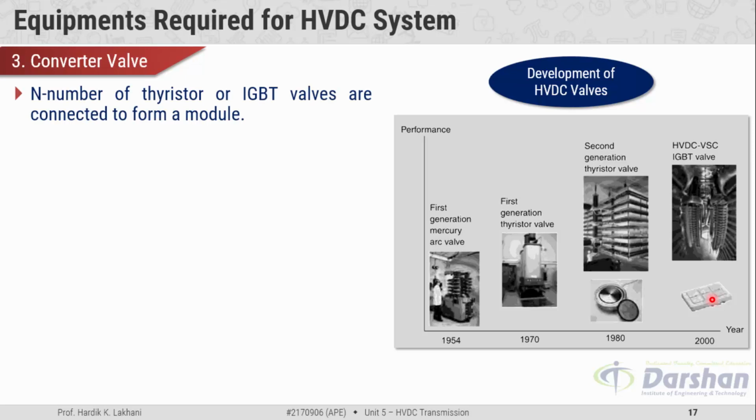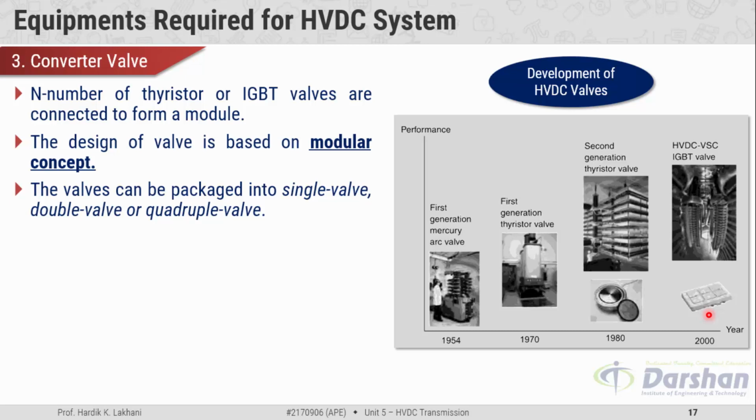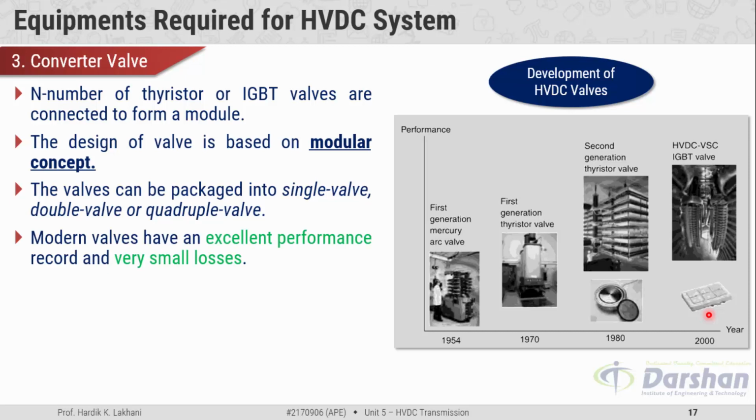N number of thyristor or IGBT valves are connected to form a module. So this is nothing but a module of IGBT. The design of valve is based on the modular concept, that is the repetition of the basic module, so we can extend or we can reduce the size of the circuit according to the ratings. The valves can be packaged into single valve, double valve and quadruple valve. Modern valves have an excellent performance record and very small losses. These are the key advantages of modern thyristor valves, IGBT valves.